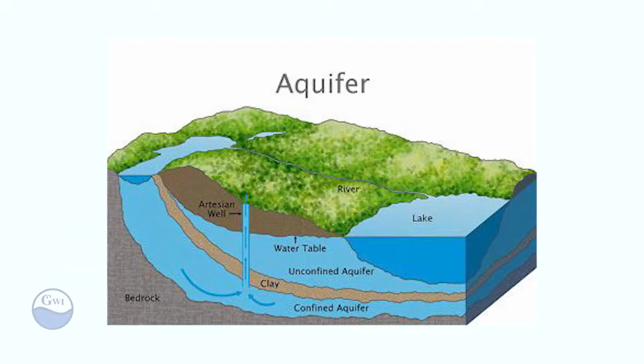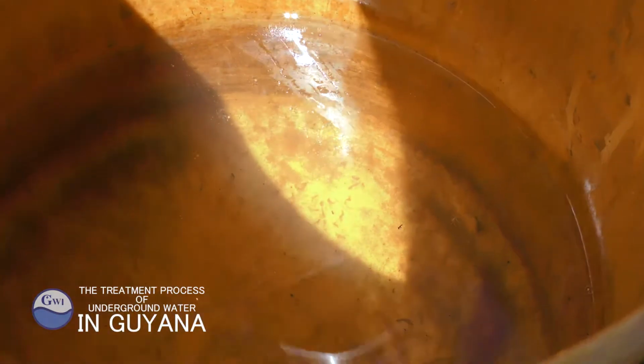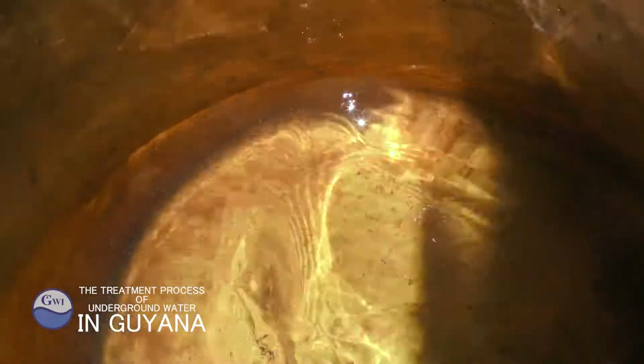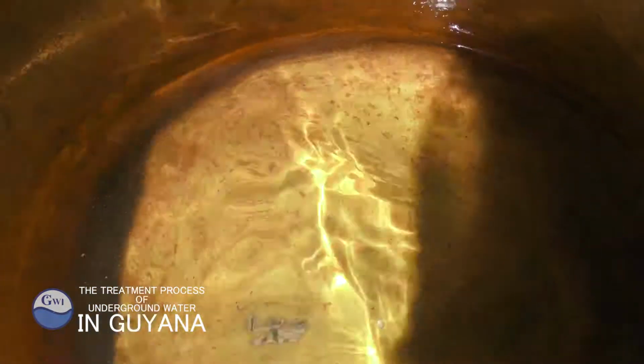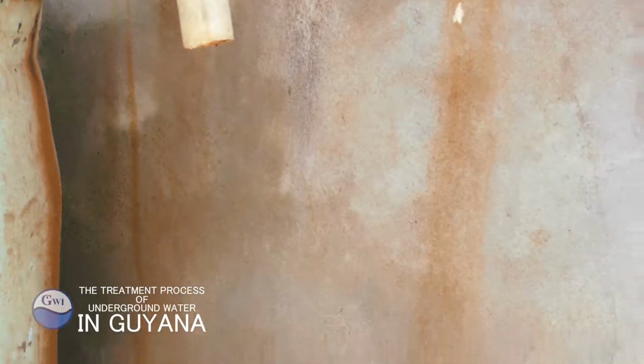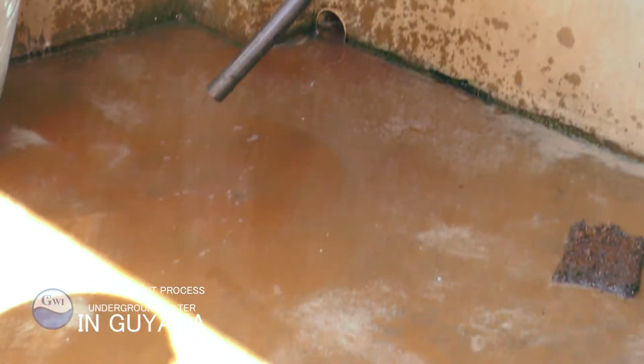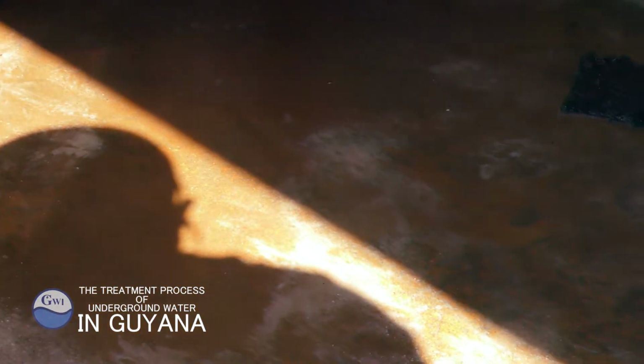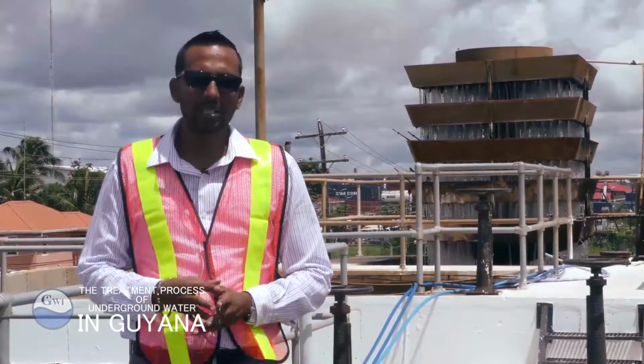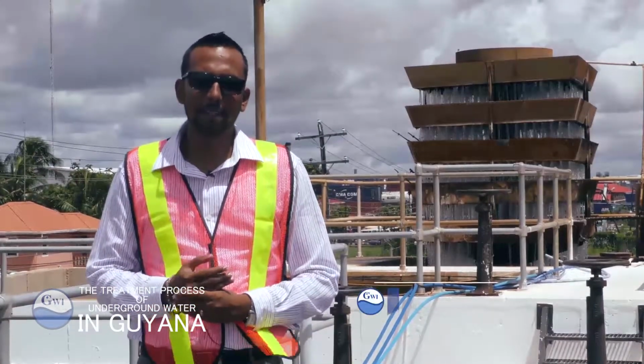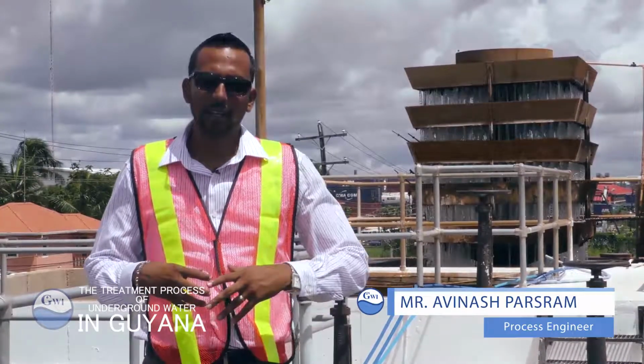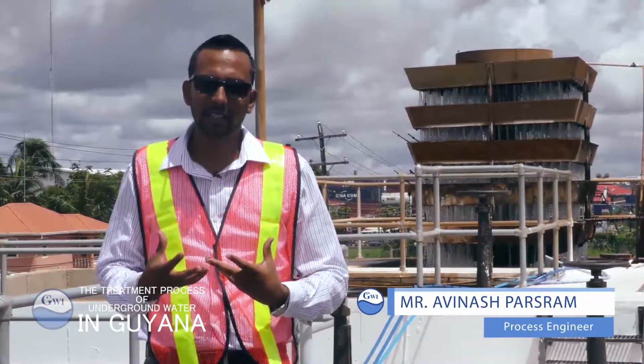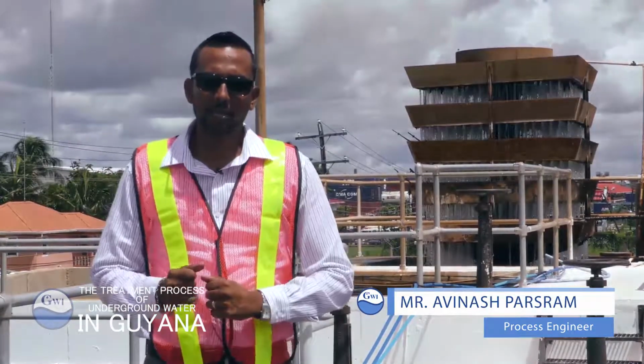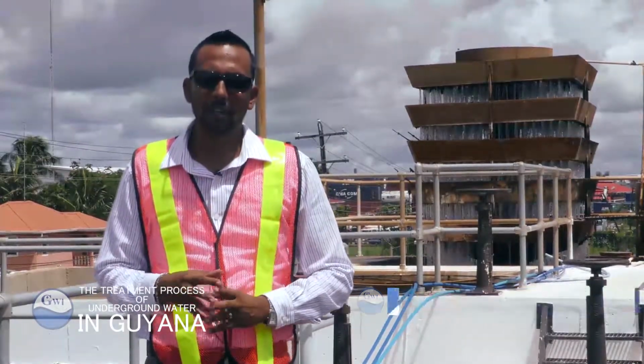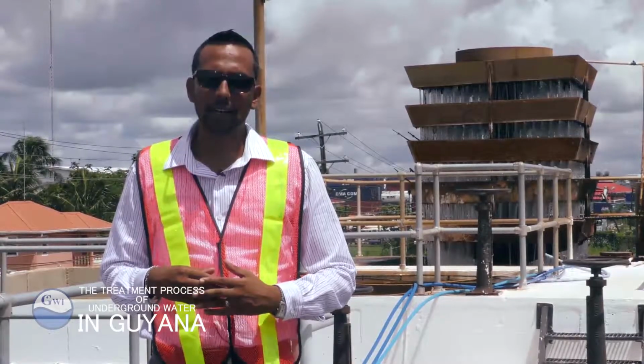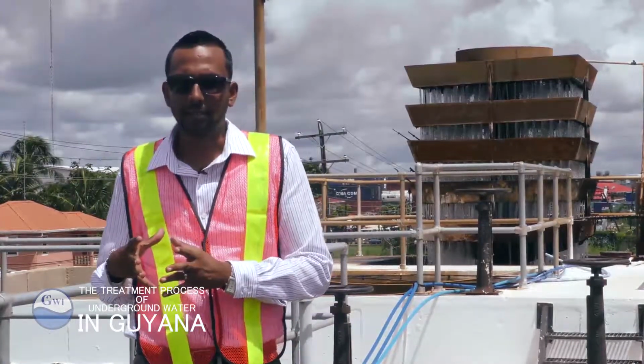The A sands aquifer is widely known for its iron content, which can range from about 1 milligram per liter to 10 milligrams per liter, depending on the location. The iron is not particularly harmful to health, but is aesthetically displeasing and can be removed by various processes. Now this iron needs to be removed. Initially, in the aquifer, it is in its dissolved state known as the clear water iron. The process can take advantage of the oxidation of the clear water iron to the red water iron.